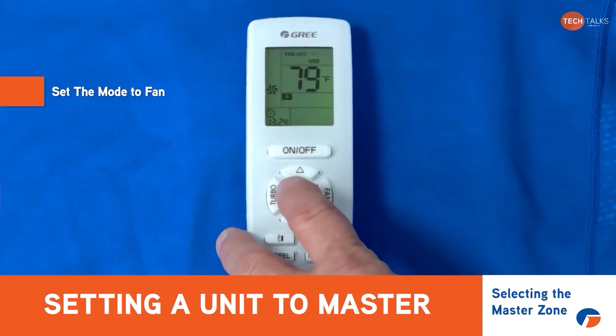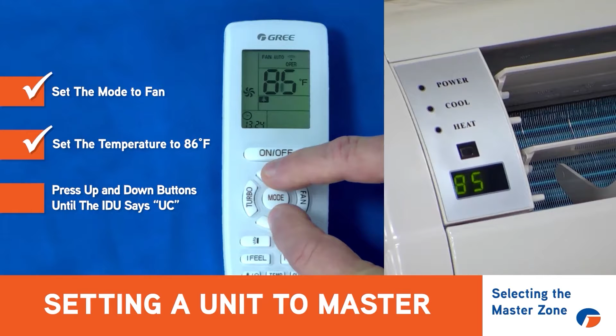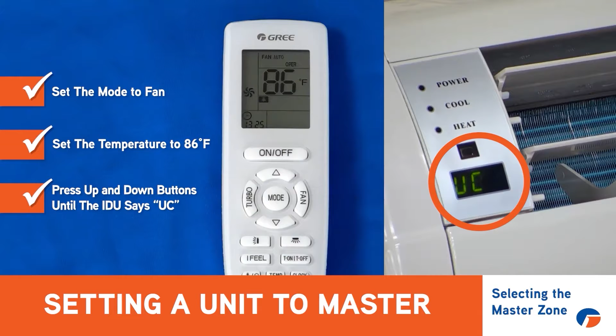In order to set the indoor unit to be the master, first we need to set the mode to fan. So I got the remote set to fan mode. Next, we're going to use the up key to set the temperature to 86 degrees Fahrenheit. Once we've got it set to 86 degrees Fahrenheit and in fan mode, then we're going to press the up and down arrow keys repeatedly, and just keep doing that until you see the indoor unit say UC. Once it says UC, you've just commanded that indoor unit to be the master indoor unit.